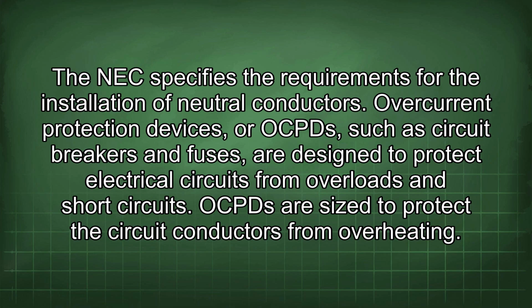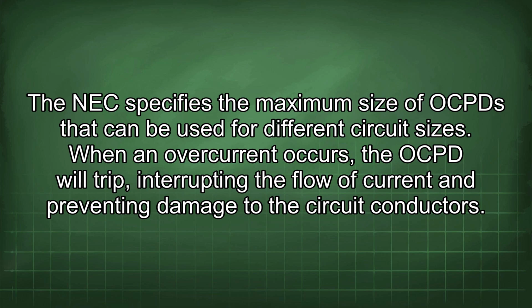Overcurrent protection devices, or OCPDs, such as circuit breakers and fuses, are designed to protect electrical circuits from overloads and short circuits. OCPDs are sized to protect the circuit conductors from overheating. The NEC specifies the maximum size of OCPDs that can be used for different circuit sizes. When an overcurrent occurs, the OCPD will trip, interrupting the flow of current and preventing damage to the circuit conductors.